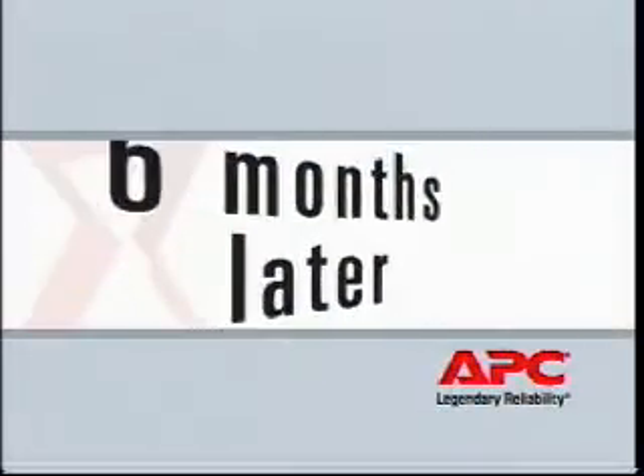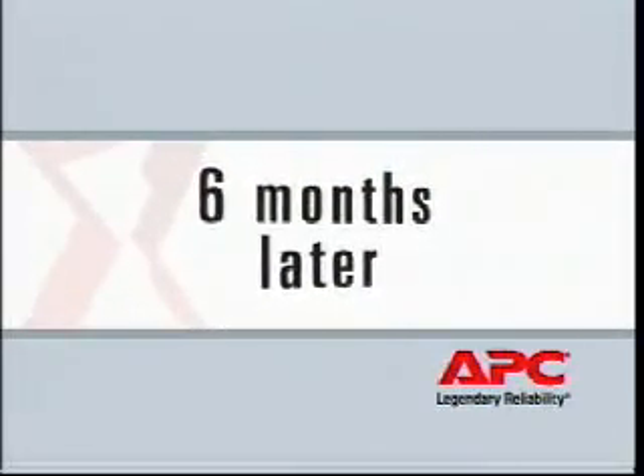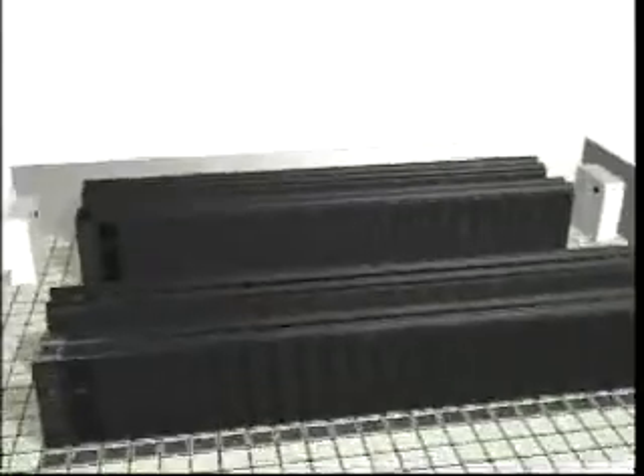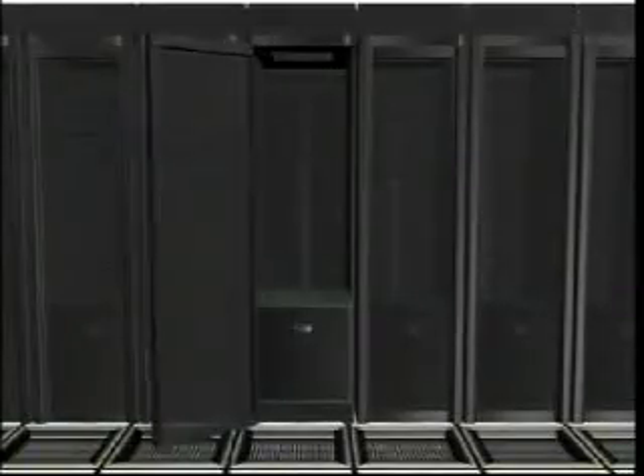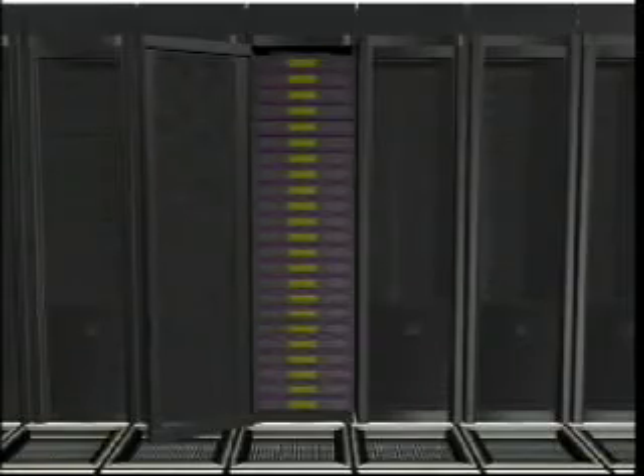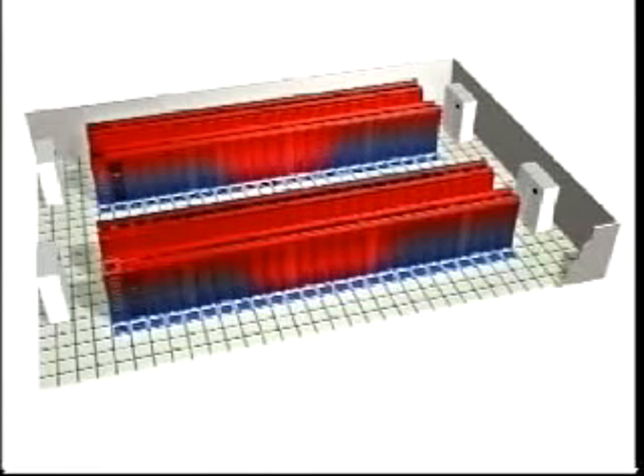To remedy this, he rearranges the tiles, moving perforated tiles to only the cold aisle and directly in front of the racks. 6 months later, it's time for an IT refresh. Newer, more dense, and more compact equipment is installed. Each device generates nearly the same heat as the old equipment. However, the racks now hold more equipment, so the overall amount of heat produced increases.